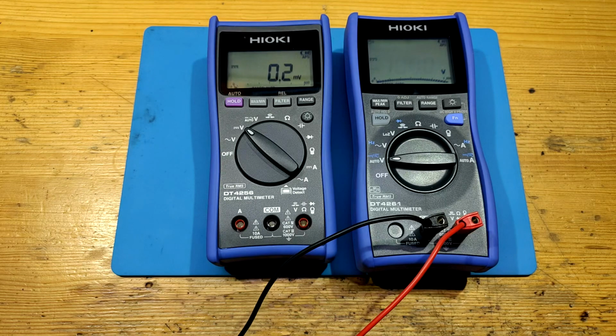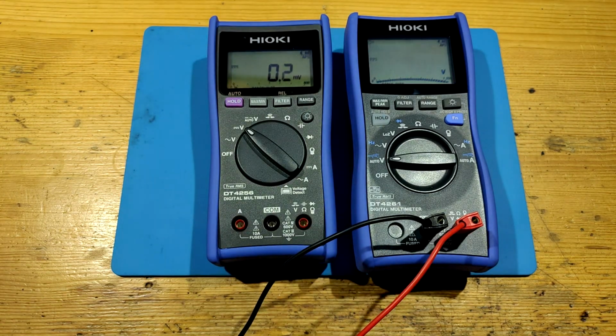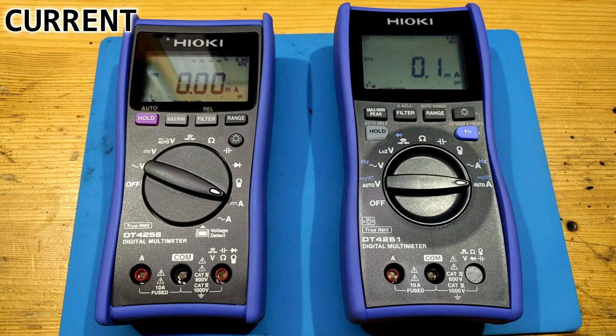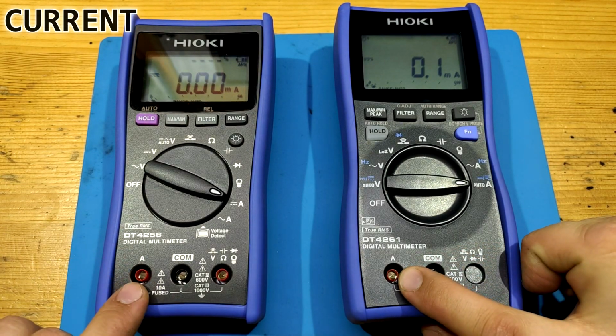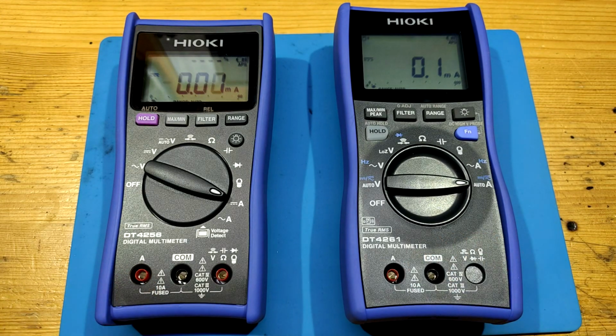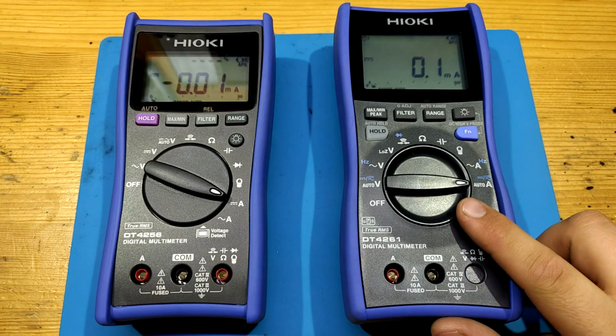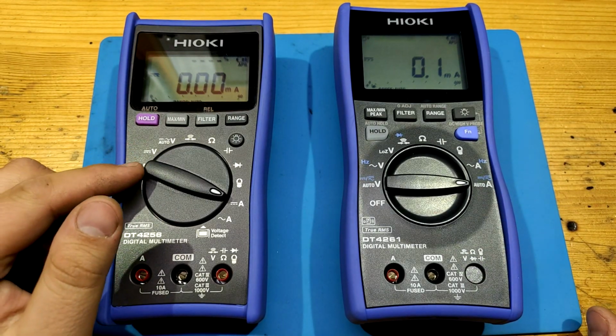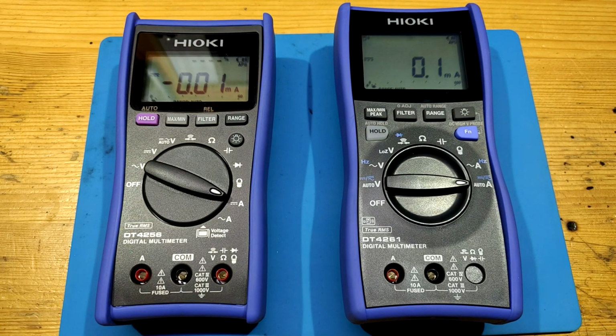It blinks the backlight. Here you can see it. Both DMMs have only the big ampere input here, 10 amps to be exact. The best resolution is down to 0.1 milliamp for 4261 and 0.01 milliamp for 4256. Maximum current of 10 amps is a little unfortunate, as I consider having a separate 20 amp input alongside separate milliamp/microamp ranges the best. These 10.00 milliamps to 10.00 amps are something in between. If it's the only option to have one current range, then okay. But again, two current ranges are far better.